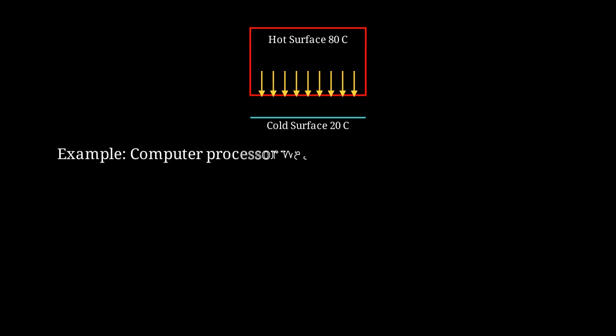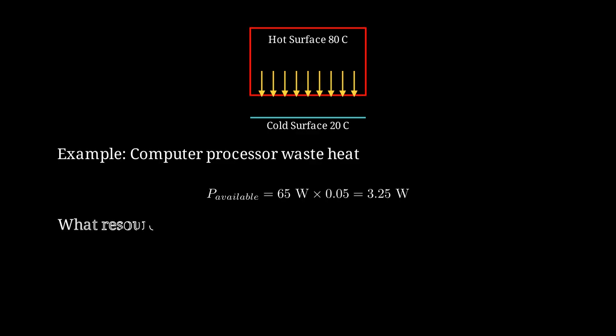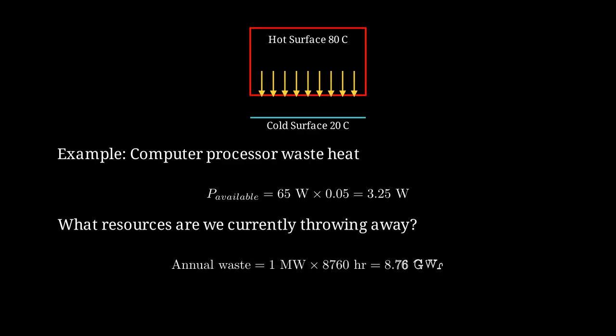A typical computer processor dissipates 65 watts of heat that could potentially be harvested. With thermoelectric generators at 5% efficiency, we can harvest about 3.25 watts from processor waste heat. What resources are we currently throwing away? In data centers, millions of watts of heat energy are simply vented to the atmosphere. A single megawatt data center wastes 8.76 gigawatt hours annually, equivalent to powering 800 homes for a year.